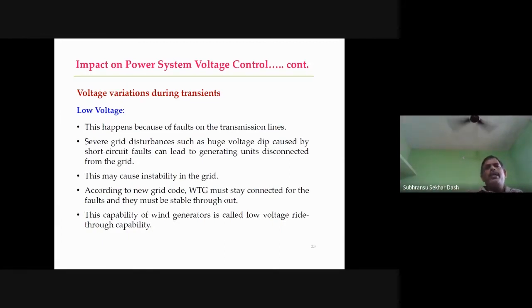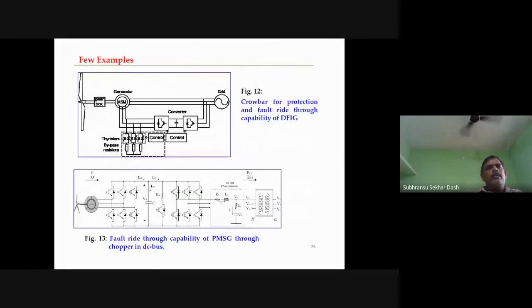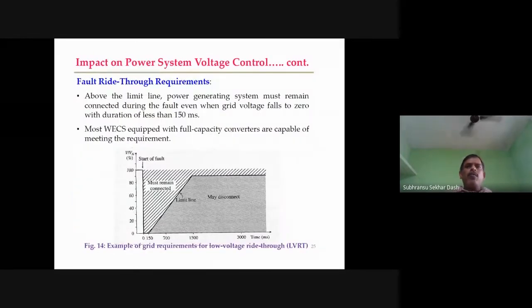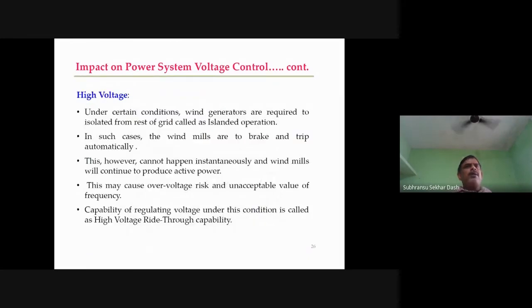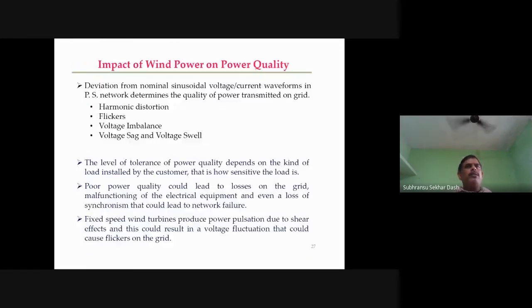According to the new grid code, wind turbines must stay connected during the fault. They must be stable throughout. This capability of a wind generator is called low voltage ride through capability. A few examples are the protections and fault ride through capability of doubly fed induction generators, then PMSG. These are the diagrams of how they meet fault ride through requirements. Impact on power system voltage control, high voltage. Impact of wind power on power quality.